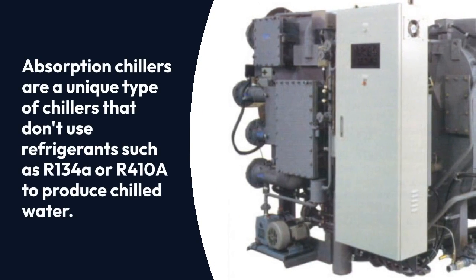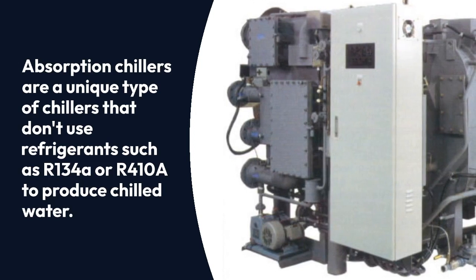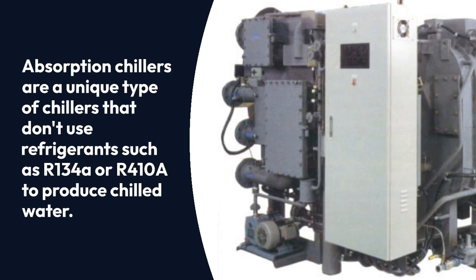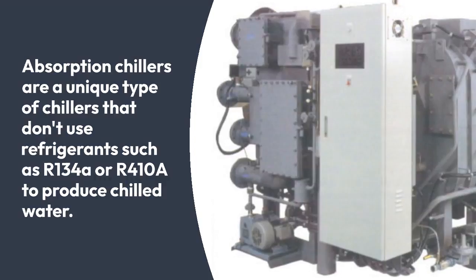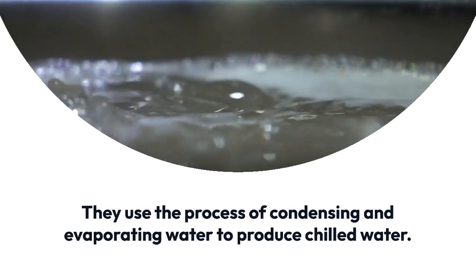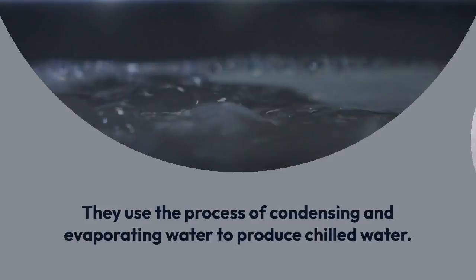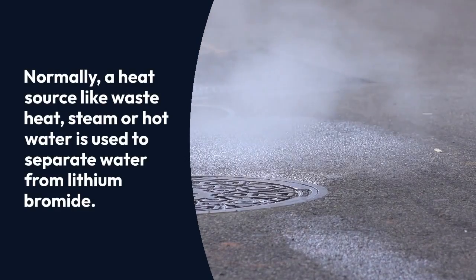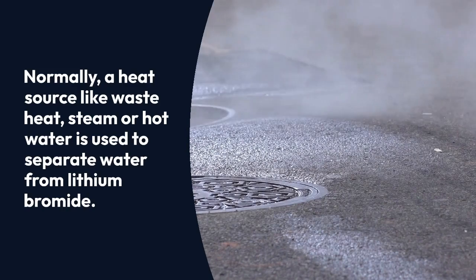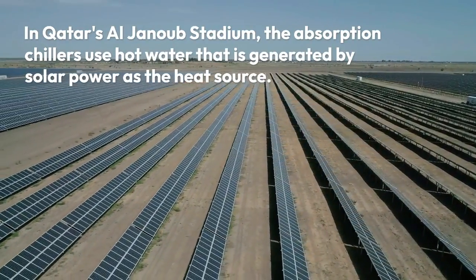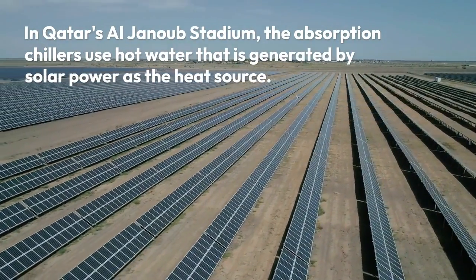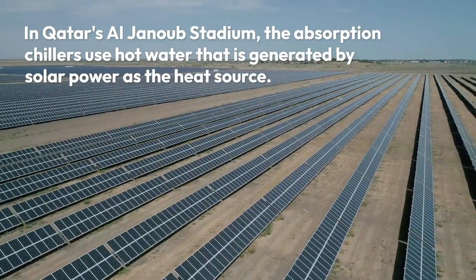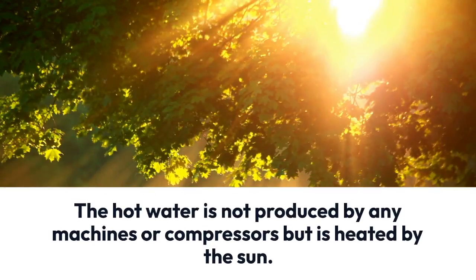Absorption chillers are a unique type of chillers that don't use refrigerants such as R134a or R410A to produce chilled water. Instead, they use the process of condensing and evaporating water to produce chilled water. Normally, a heat source like waste heat, steam or hot water is used to separate water from lithium bromide as part of the normal operation of absorption chillers. However, in Qatar's Al Janoub Stadium, the absorption chillers use hot water that is generated by solar power as the heat source. The hot water is not produced by any machines or compressors, but is heated by the sun.